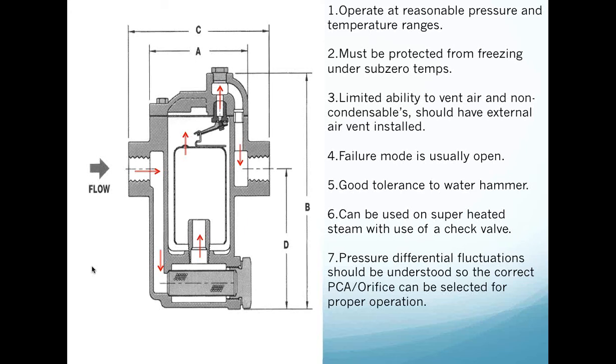And I want you to know that on the top of every inverted bucket steam trap, there is a tag that will give you the PMO, the maximum operating pressure, and/or a stamp, with a set of steel dies that somebody will take and stamp. A 60, a 30, a 125. That number will be the max differential that that inverted bucket steam trap can actually work within. I need you to know your equipment. I need you to be able to put your hands on it with a magnifying glass and a flashlight, and I want you to make sure that as you travel your campus, your facility, you understand what those differentials are built into the inverted bucket steam trap population that you use. It's very, very important because it also tells us what the actual capacity of this trap is.